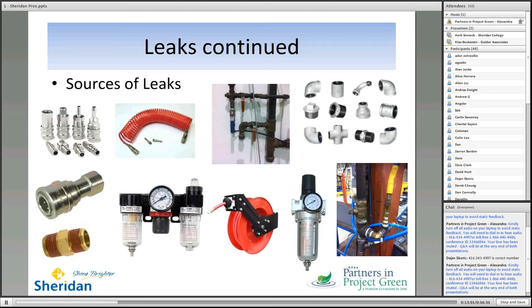Also hoses. More often than not, we find hoses in plants that have hose clamps, the standard garden hose clamp. That almost always leaks. So if I'm walking through, I would find maybe 75% of the hose clamps are leaking in some way. The preferred alternative with compressed air is a crimp-on connector. So it's worth the extra investment to get that connection right. And also what we see are those plastic hoses like you see leading to the air blow-off gun, or sometimes fed to a regulator assembly on the back of a CNC machine. If they're fairly lightweight, they end up splitting, and you get a good hiss out of those. So it's worth the investment in a heavier duty hose, but also paying attention to the fact that those are going to begin to wear.